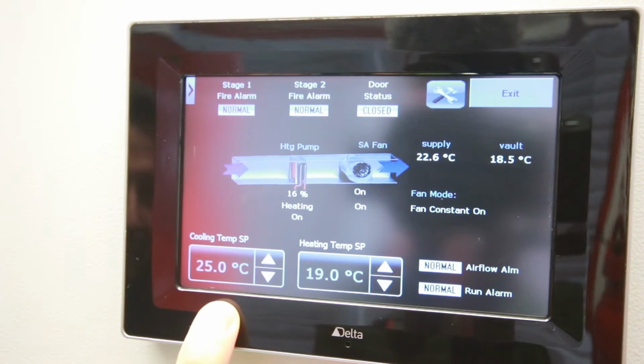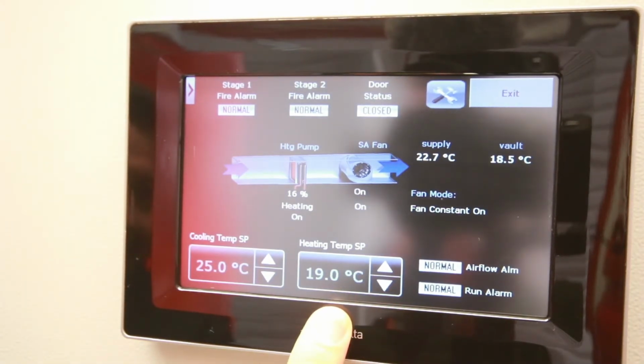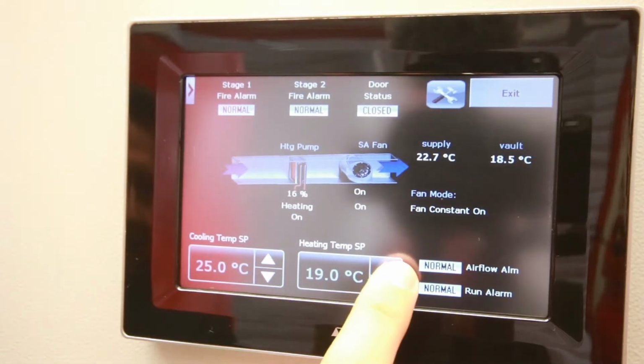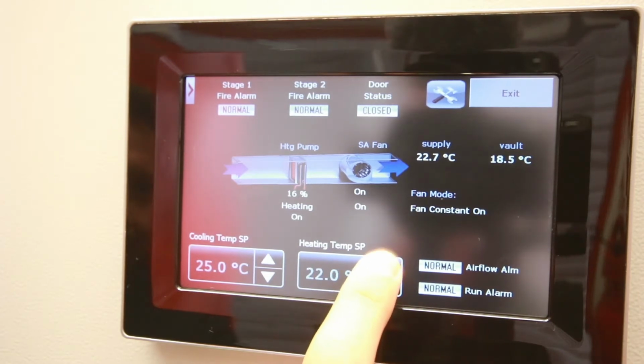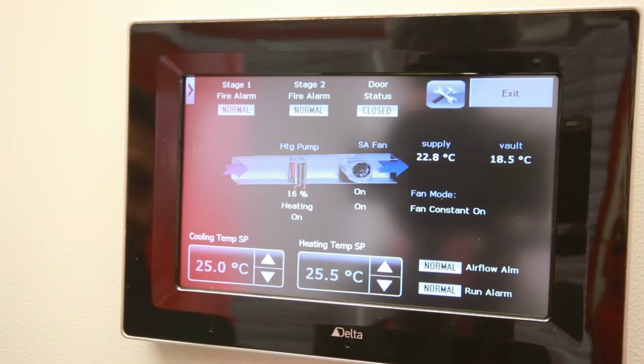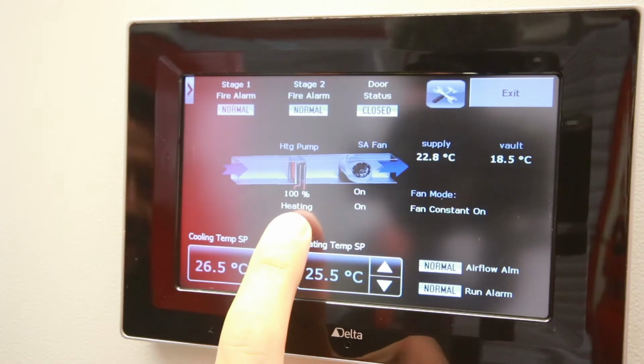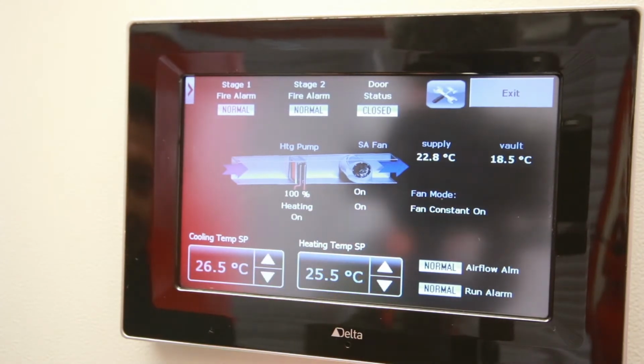In the bottom corner here we have our cooling temperature set point. Once the internal temperature of the Firevault reaches plus 25 degrees, our cooling system will kick in to reduce the internal temperature. Conversely, our heating temperature is set at plus 19 degrees. If the store temperature inside the Firevault drops below 19 degrees, our heaters kick in and the store begins to heat. We can manually demonstrate this, for example, by increasing our required heating temp point. And you can see this has caused the heater to kick in 100%, so we can see it's operational.